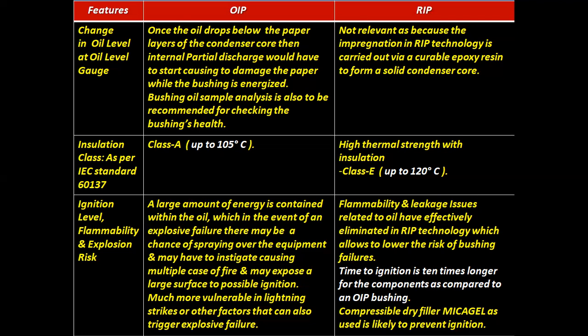Insulation class as per IEC standard 60137. Class A in the case of OIP, that is, it can withstand temperatures up to 105 degrees centigrade. For RIP bushing, high thermal strength with insulation class E, that is, up to 120 degrees centigrade. We know the insulation classes Y, A, E, B, F, H, C. You must remember the classes of insulation: Y, A, E, B, F, H, C.